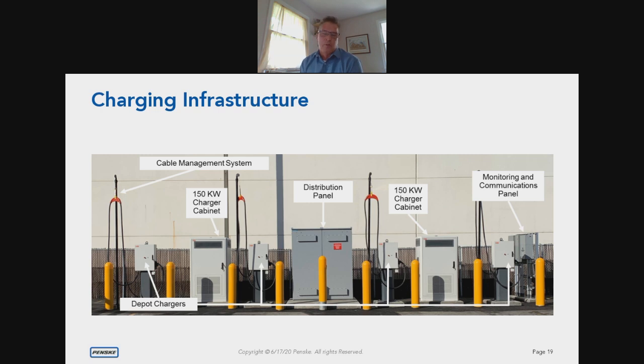Most of you will see in the setup we chose a 150 kW charger, with a cabinet that supports your charging networks. For this system, the ABB, we had 2 dispensers per charger, replicated down through in a fashion that worked for us. You'll also see a main distribution panel, very critical to the operation. With the special EV rates that exist with utilities, having a separate meter set up for your EV infrastructure is very beneficial in the long run, allowing for easier construction and installation rather than tapping off your building depending on where you want to engage your system on the lot.